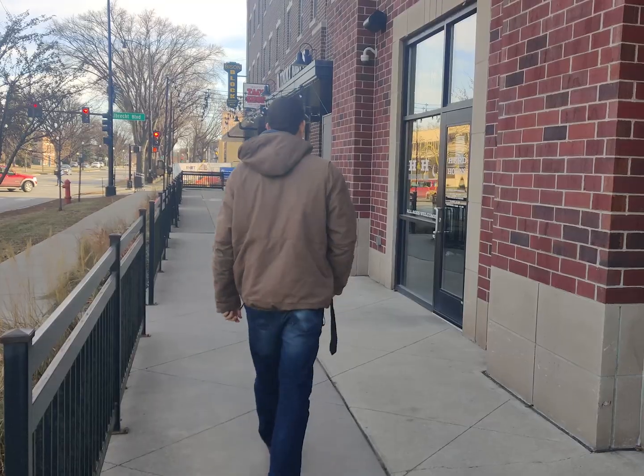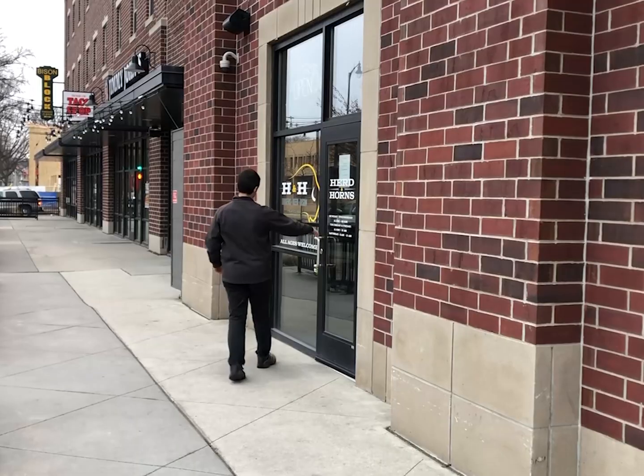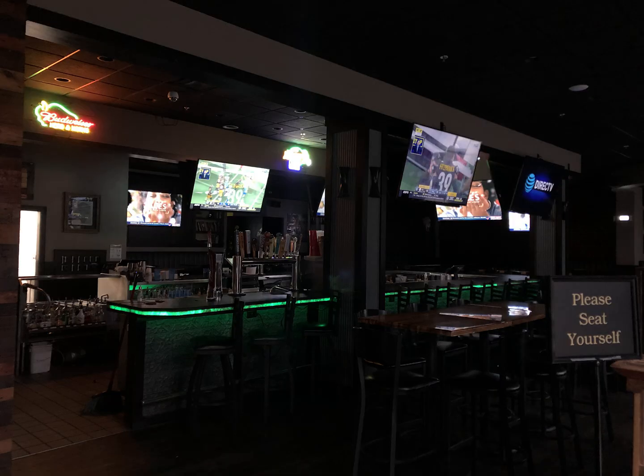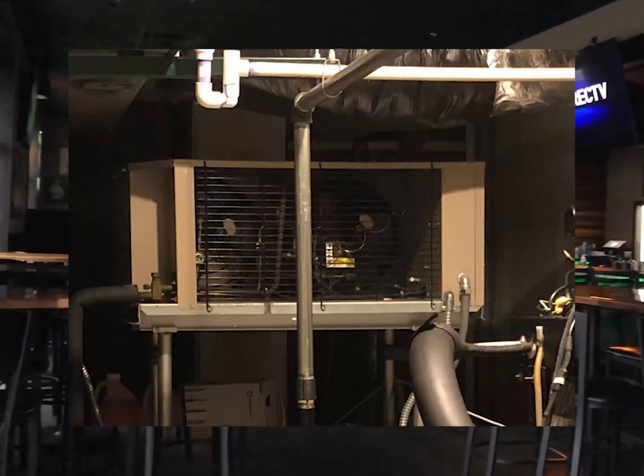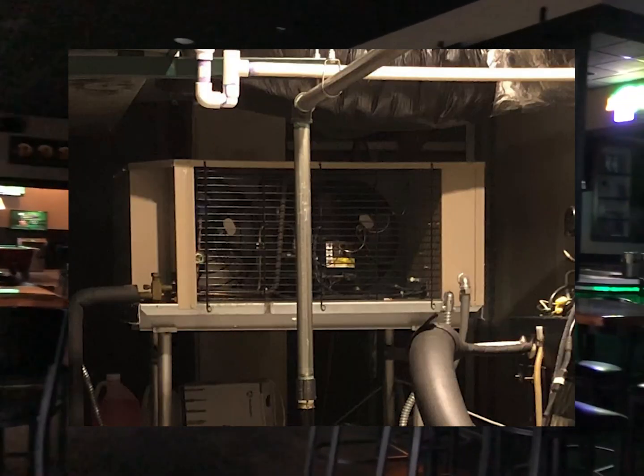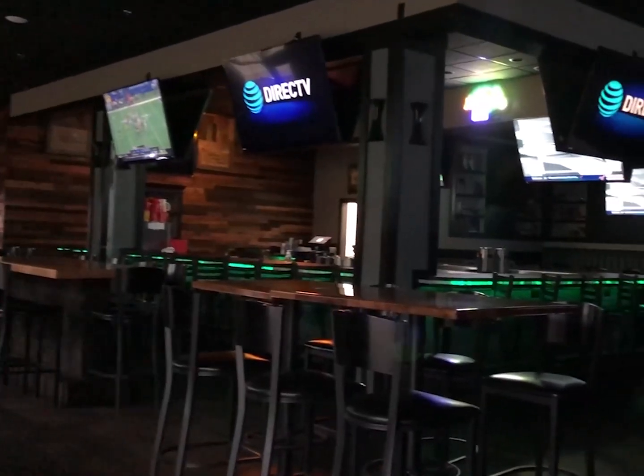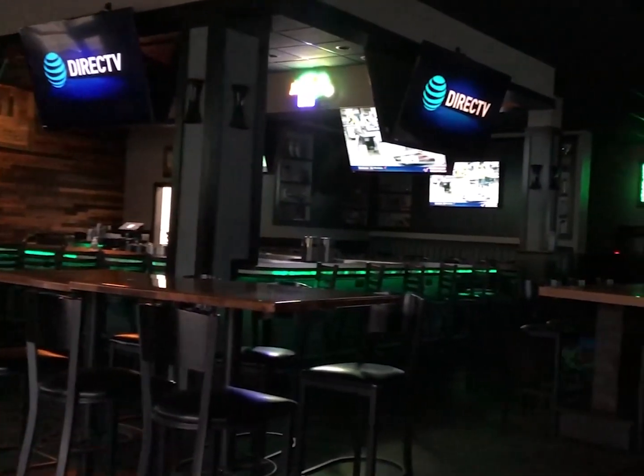The heat transfer for energy savings team created a heat recovery system at Herd and Horns located on 12th Avenue to reduce the restaurant's energy consumption and operating costs. Hot air was exhausted from a condenser into the open attic space above the dining area. This increased the ambient temperature around the condenser and in the attic, increasing the demand for air conditioning.